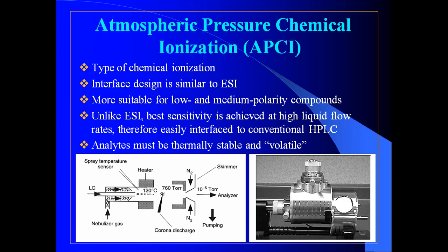The corona discharge in the APCI source is formed by three major electric field and fluid flow elements: the corona discharge needle, a curtain plate, and the orifice lens. The purpose of the corona discharge is to produce ionization of the trace species or sample gas.